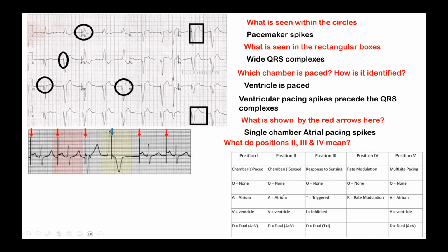It is the heart's natural or intrinsic contractions which are sensed, so that the electrical stimulation by the pacemaker can be stopped during that time. So the sensing is mainly for the intrinsic activity of the heart. The response to sensing can be to inhibit, to trigger, or to do both. And rate modulation can have a normal stimulatory mechanism or no stimulation at all.